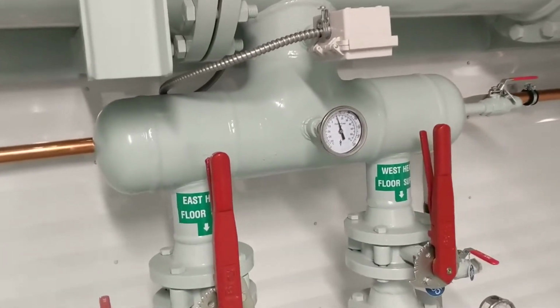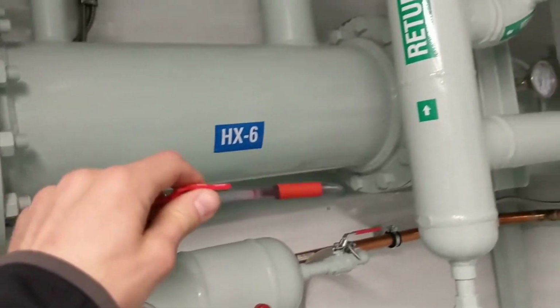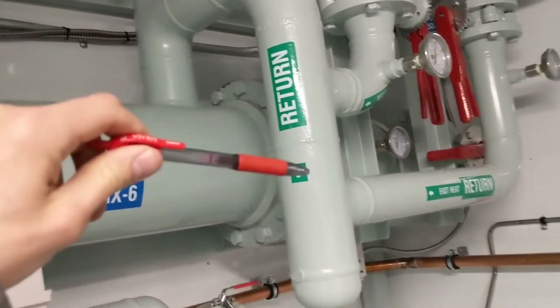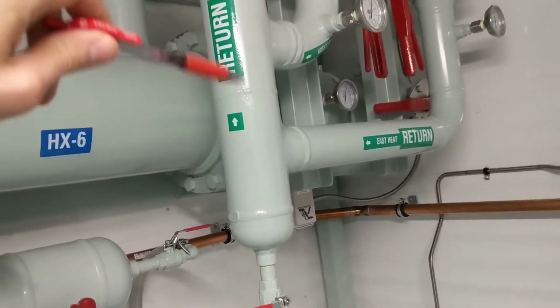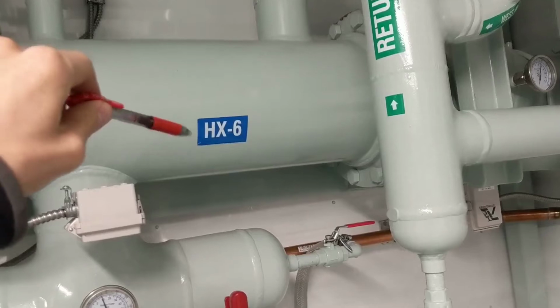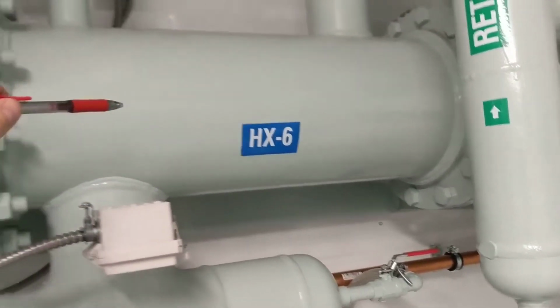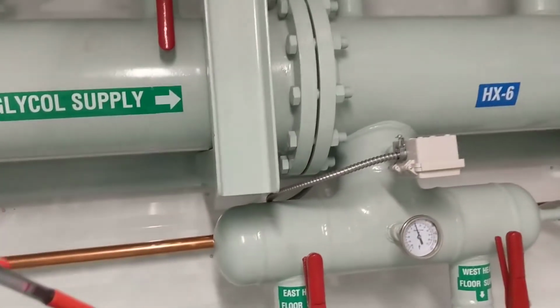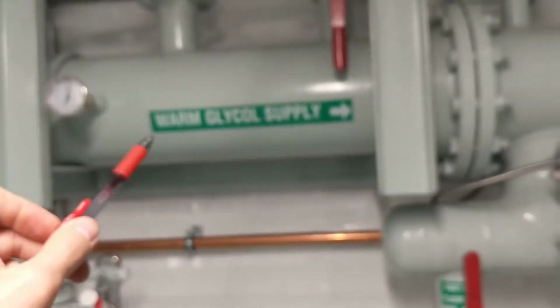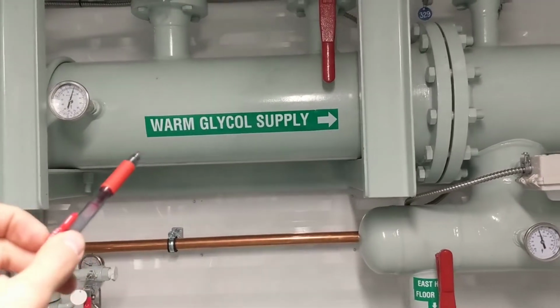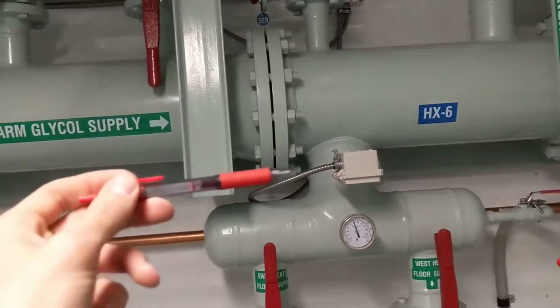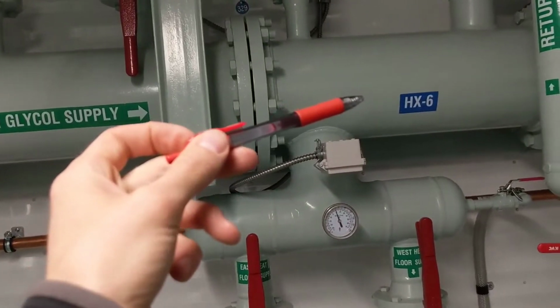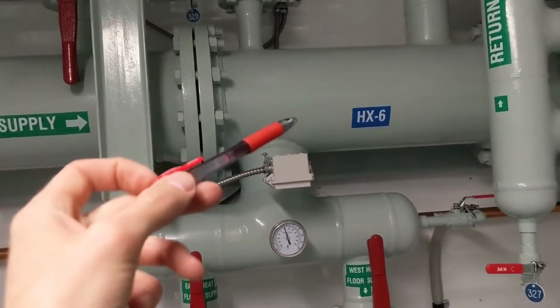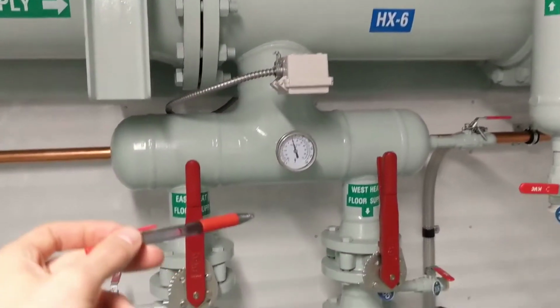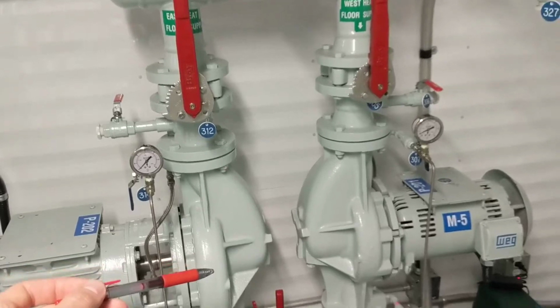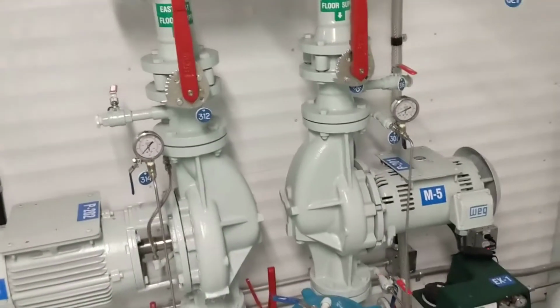Your heat floors are going, your brine is coming back this way. So as the brine circulates, it's coming back here. It's going through this heat exchanger HX6, which is a shell and tube style of heat exchanger, and it's exchanging its heat with the warm glycol. So the warm glycol is coming this way. It's giving its heat to the brine, and as the brine picks up its heat, it is fed out through here, and it's fed to each of the arena warm floors.